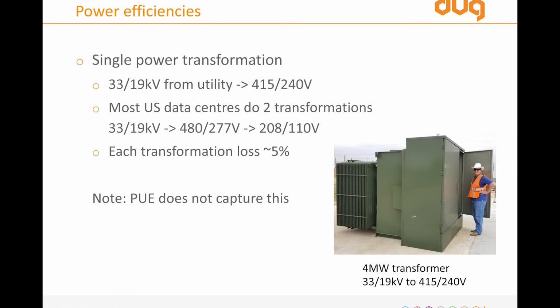So, some of the things we did. Power efficiencies. These are the big ones. Single transformation. We take 33,000 volts, 3-phase, from the utility. We convert that directly with one transformer, and there's one of them in a stunningly good-looking bloke there. We convert that to 415 volts, so 240 volt single phase in the US, at 60 hertz. So it's not quite Australian power, but it's very close. Okay? You would not believe how difficult this makes life in the US. But all the fun guys in town are starting to do it.